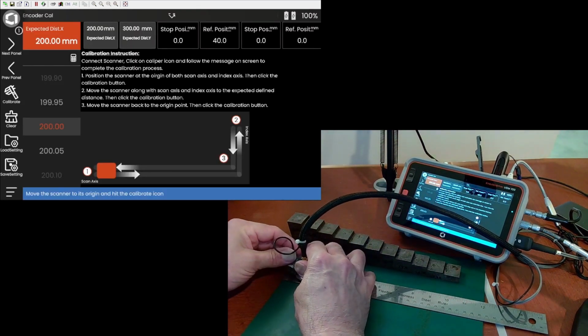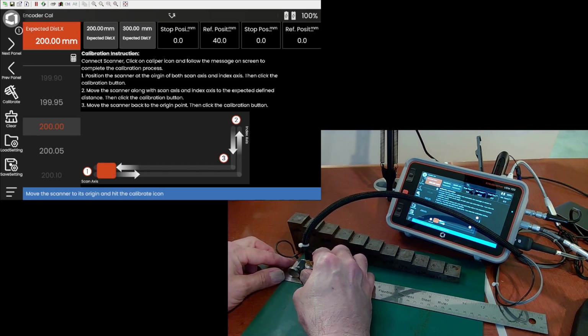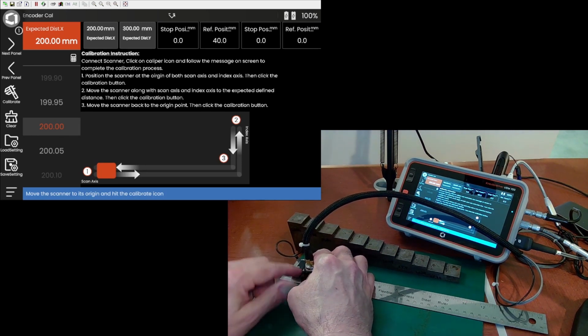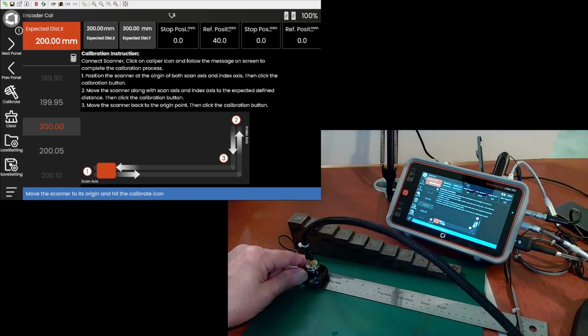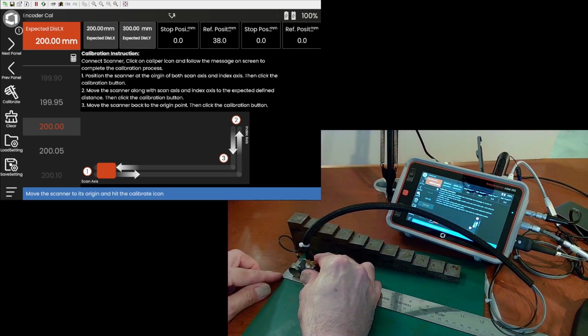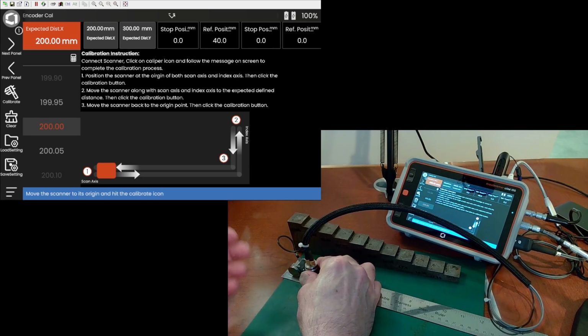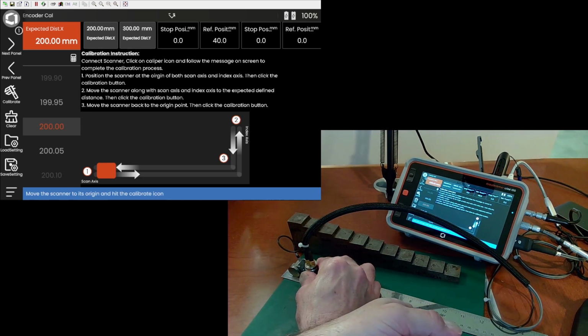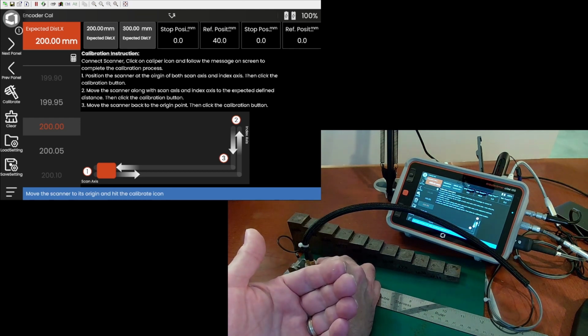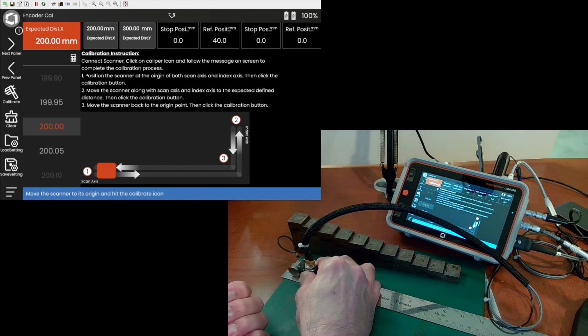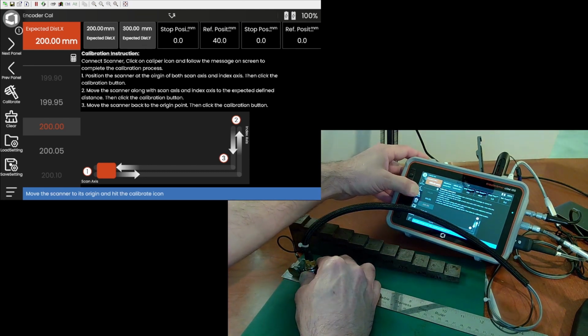I'll put the probe down, and I'll set the bottom of the wheel right at 2 on my scale. Okay. The encoder calibration happens in 2 steps. We set a starting point, hit calibrate, we move it the expected distance, and we'll move it 200 millimeters along the ruler, so from 2 to 22 centimeters on the ruler. Hit calibrate, and then it's going to want to check backlash, so we'll get back to our original position at 2 centimeters and hit calibrate one more time. So we'll do calibrate.